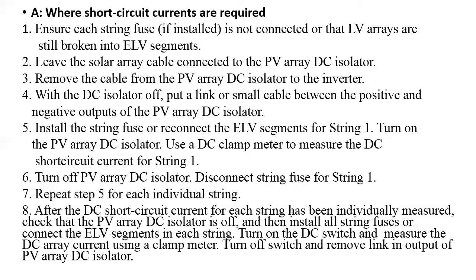And of course, for testing, that is, measuring the short circuit currents of the strings and the array, there are two cases: where short circuit current measurements are required and where they are not required. For that there is a simple procedure, given here in some of the US standards, which ensures where short circuit currents are required and where they are not. And there is a procedure they have followed for measuring the short circuit.